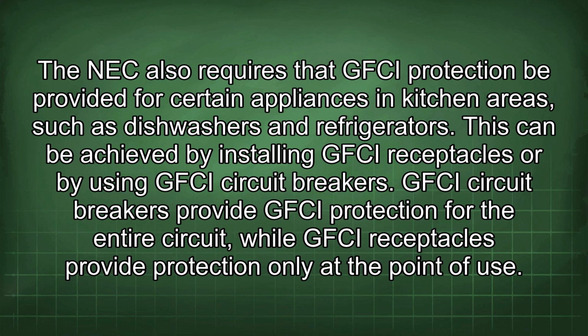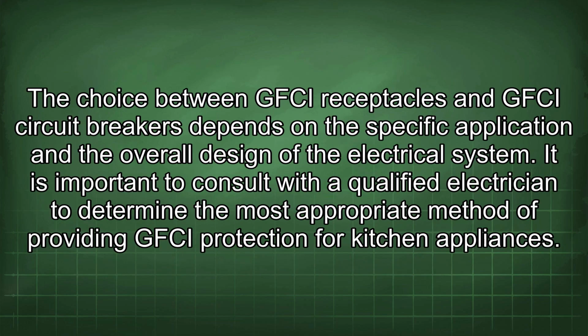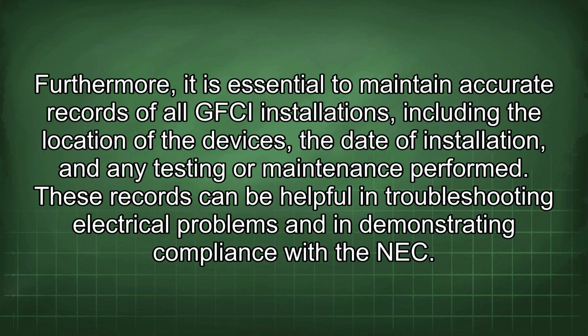GFCI circuit breakers provide GFCI protection for the entire circuit, while GFCI receptacles provide protection only at the point of use. The choice between GFCI receptacles and GFCI circuit breakers depends on the specific application and the overall design of the electrical system. It is important to consult with a qualified electrician to determine the most appropriate method of providing GFCI protection for kitchen appliances. Furthermore, it is essential to maintain accurate records of all GFCI installations, including the location of the devices, the dates of their installation, and any testing or maintenance performed. These records can be helpful in troubleshooting electrical problems and in demonstrating compliance with the NEC.